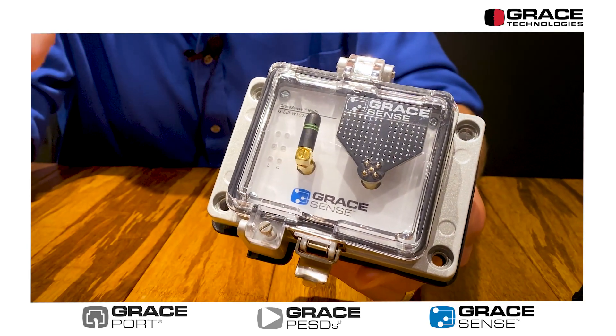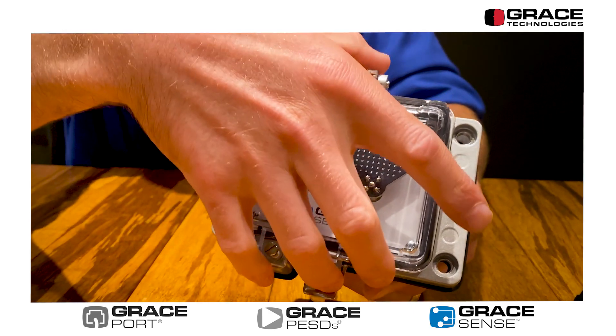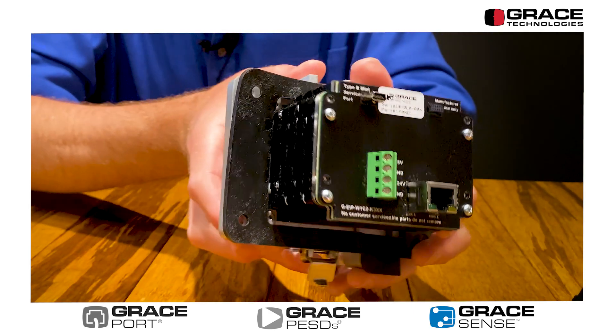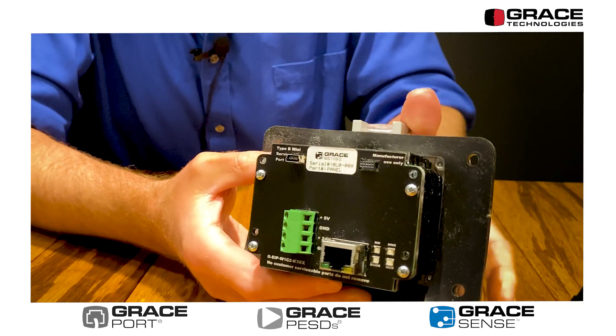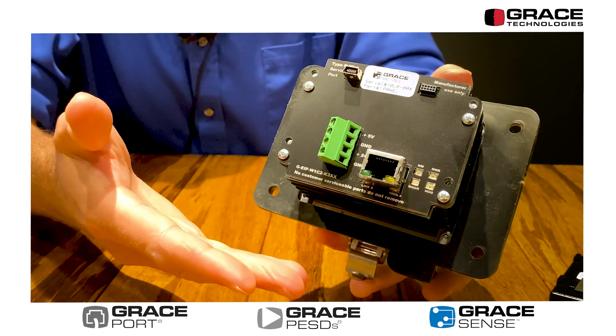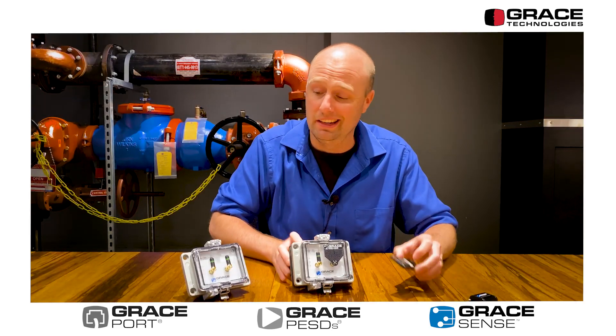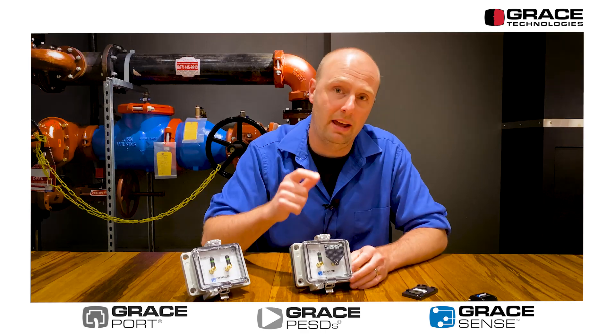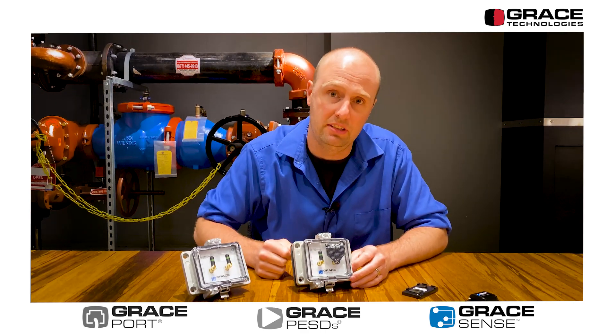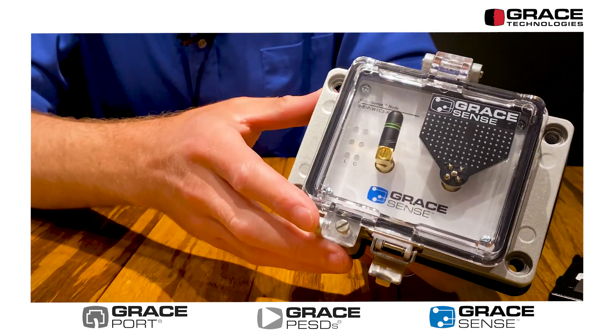In this case, we're showcasing a combo gate. We call it a combo gate because it has both cloud and control capabilities. On the backside of this device, we build it out with an Ethernet port, and that allows this gateway to take data from any number of panel mount nodes and vibration nodes and push that both to the cloud — in this case via LTE — and to the PLC over Ethernet IP or Modbus TCP/IP.